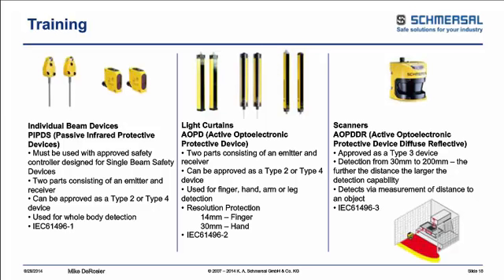One of the common mistakes is a light curtain replacing a fixed guard or door on a machine because the frame is there and it's convenient to mount the light curtains right there. Not knowing the stop time of the machine, you find too many times that light curtains are mounted too close to the machine — somebody can still potentially get hurt if they reach through that light curtain, expecting it to shut down the machine at the exact moment they trigger it.